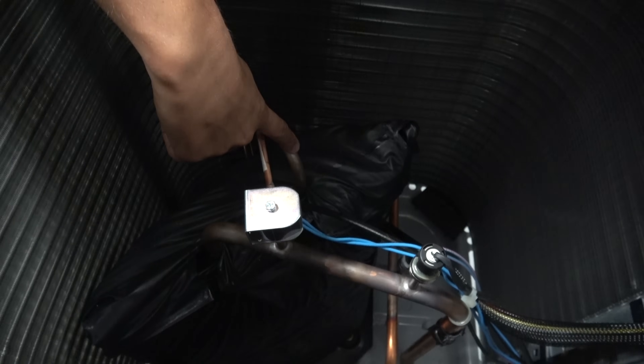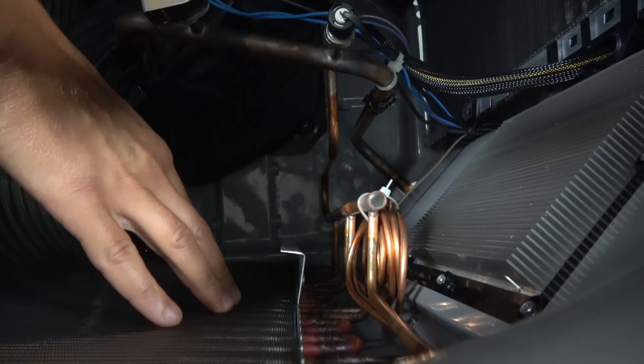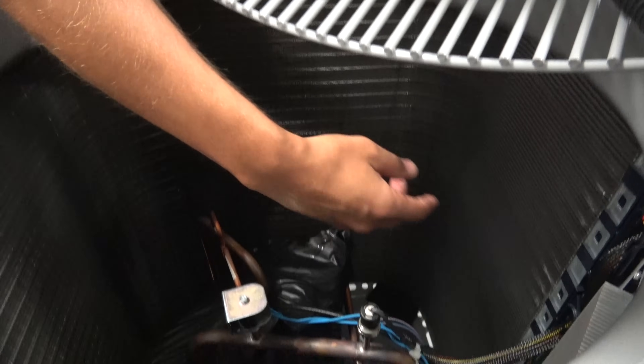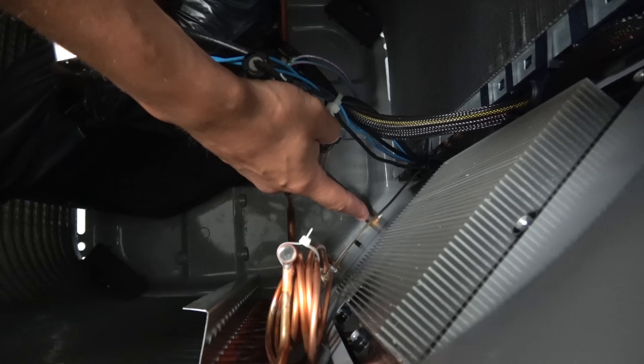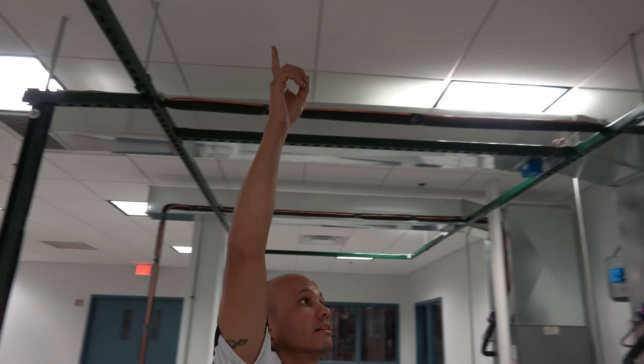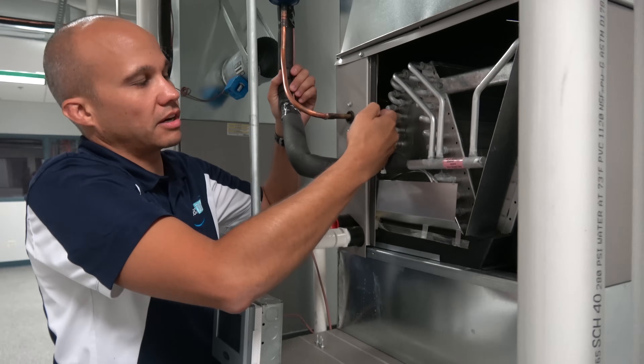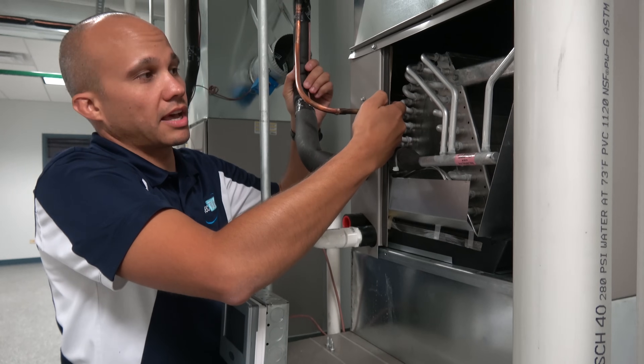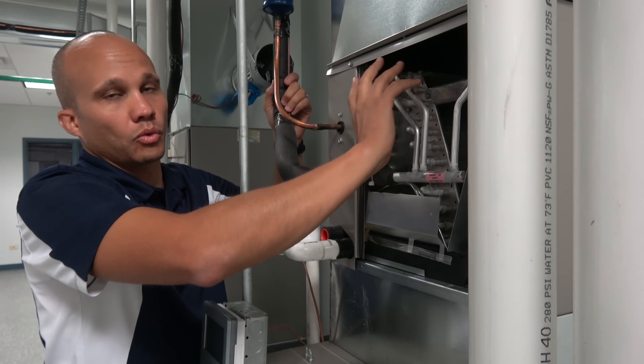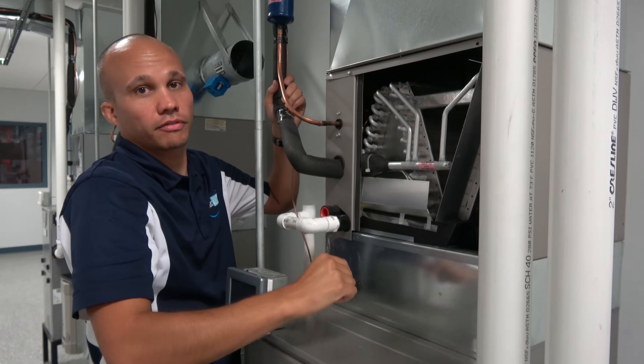The refrigerant leaves the compressor on the hot gas line. Follow that pipe all the way around — the hot gas line goes into the condenser coil, where it uses all that surface area to reject heat to the outdoors. Then it comes back out of the condenser coil into the liquid line, which makes its way back through the piping system to the indoor side of the building. The liquid line comes in, goes into our TXV — which is a little tough to see in here — and the TXV's job is to lower the pressure and hence lower the temperature, so we have cool refrigerant entering the evaporator coil. Now it's cool enough to absorb more heat from the air, and the cycle repeats — hence why we call it the refrigeration cycle.